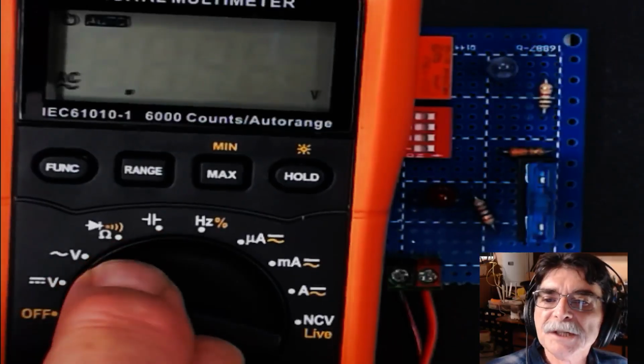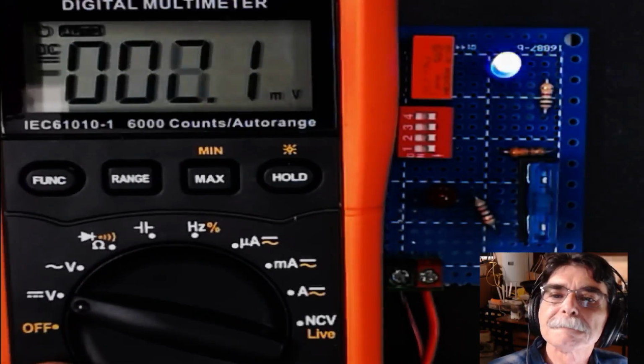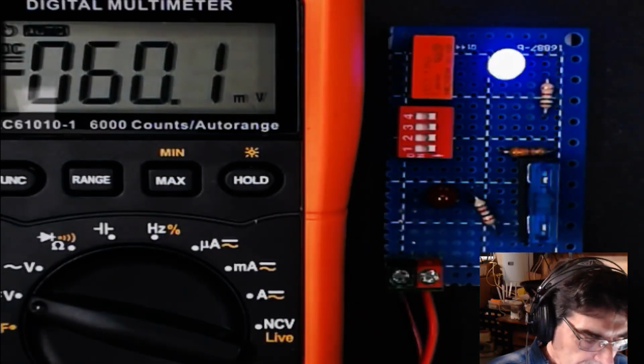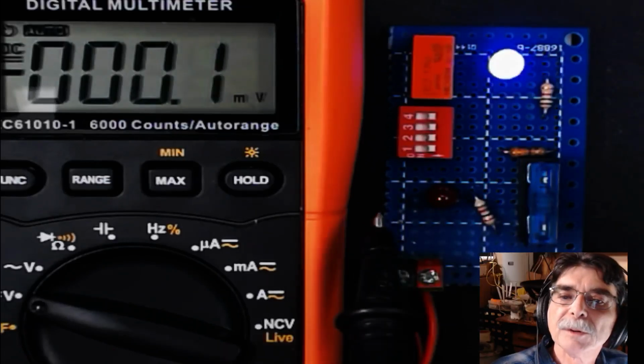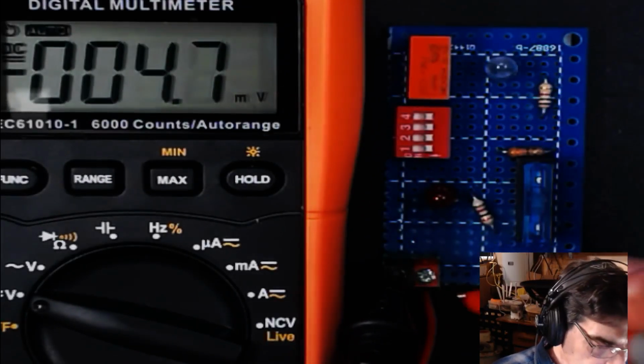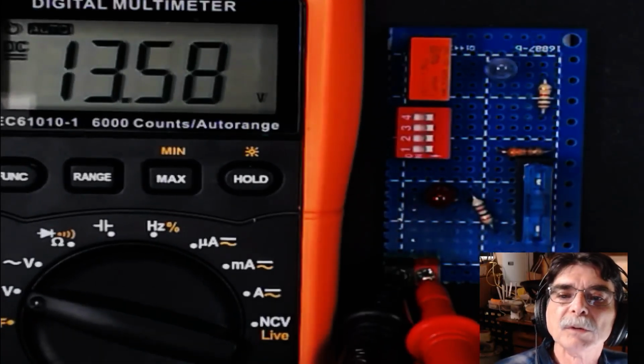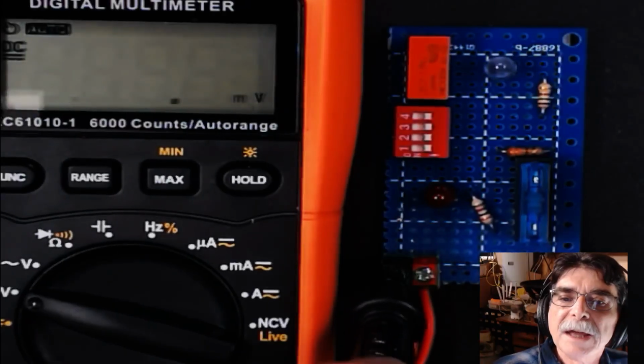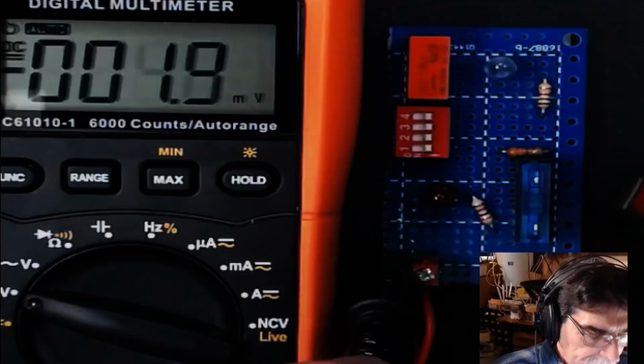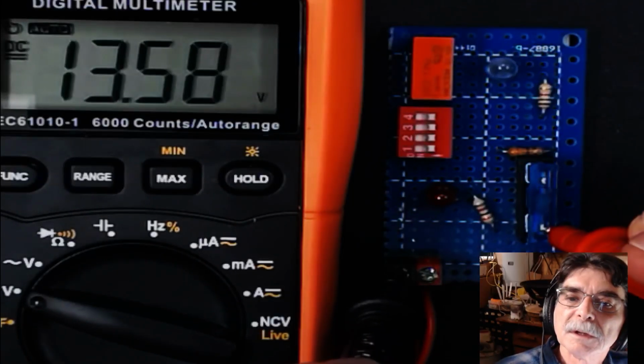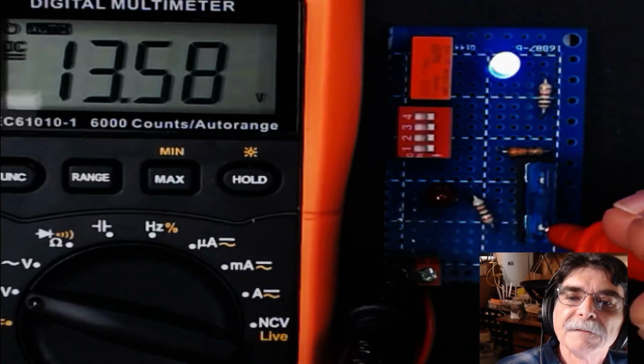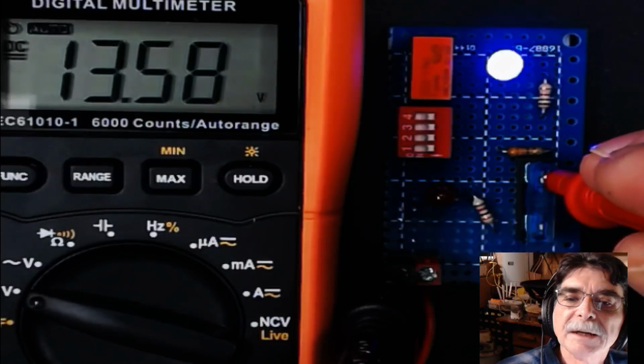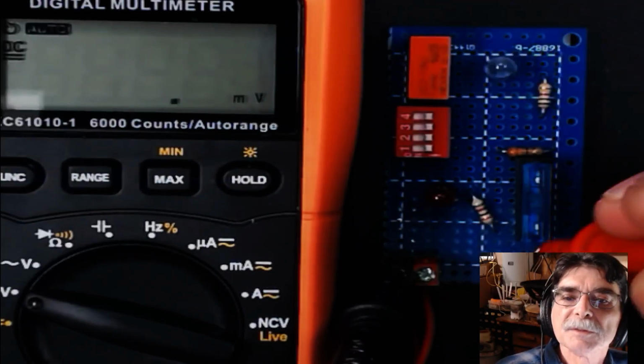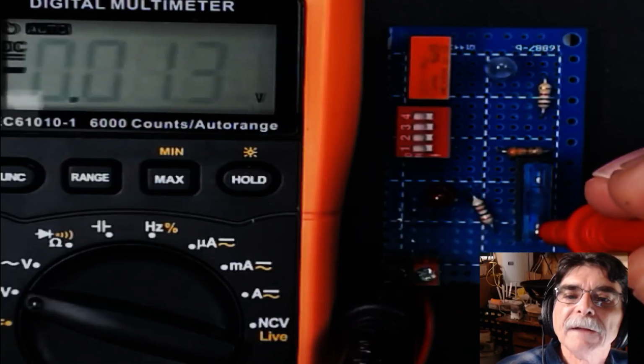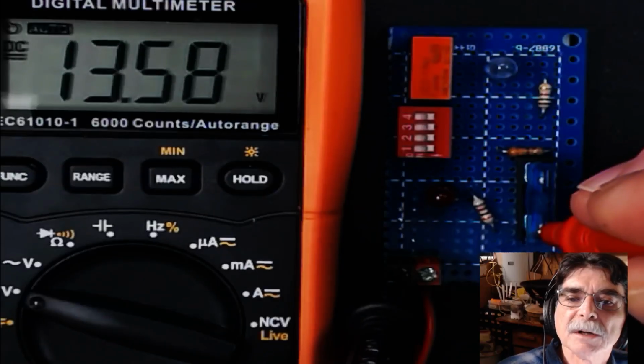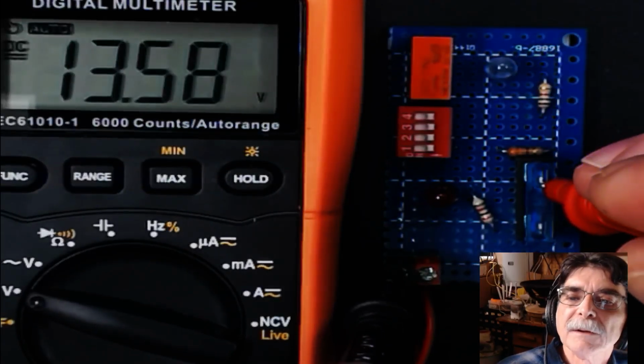We're going to set our meter to voltage DC, so volt DC. We're going to measure the voltage going in. I got the black probe on the negative and the plus probe on the positive. And we have 13.58 volts. If I keep the meter negative on the negative battery and I put the probe on the fuse, I get the same voltage, 13.58. If I put the meter probe on the other side of the fuse, I get the same voltage. And the reason is that the fuse is passing the voltage from one side to the next. So this is a good fuse. And we just proved that because we can see the same voltage on either side of a fuse without using continuity.